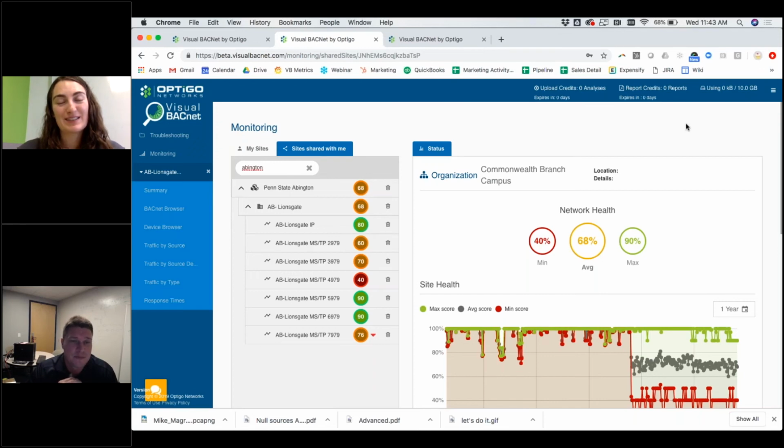Yeah, that doesn't surprise me. So here we can see the main reasons is that there's communication problems on the inside of the building, and because you're heavily integrated, that's even worse. If you're doing a lot of integration, you're relying on those TEC units to give us the cooling requests. If it can't communicate that, then the primary equipment's not going to perform to what you need to maintain the building.